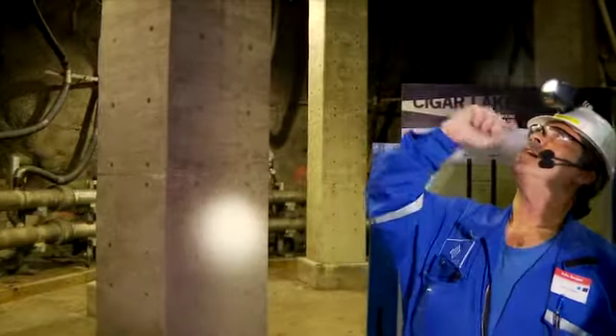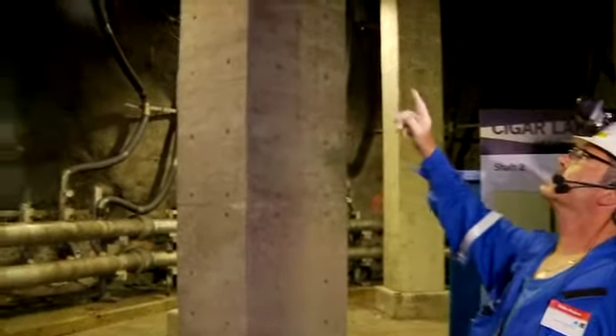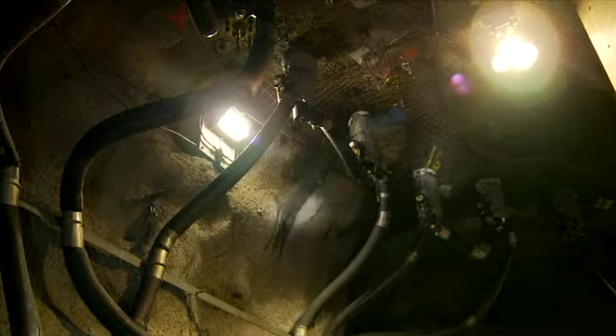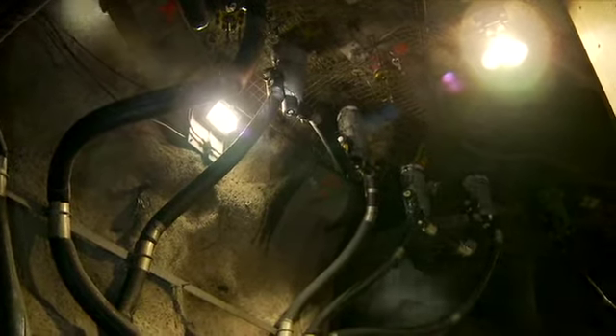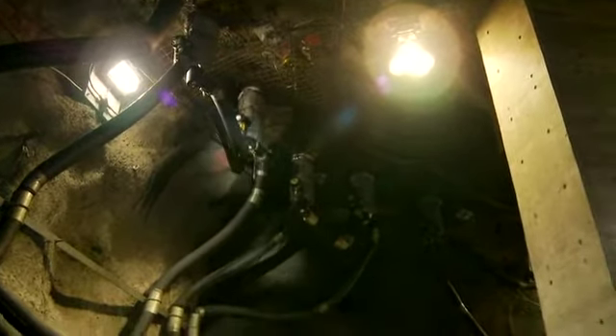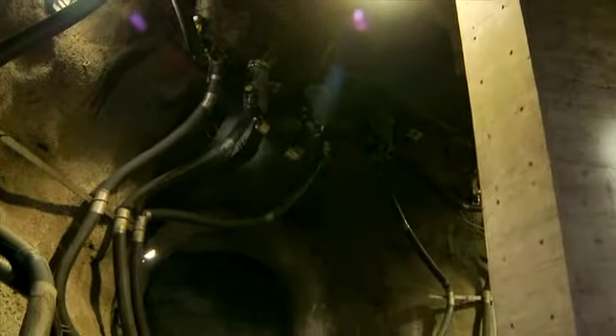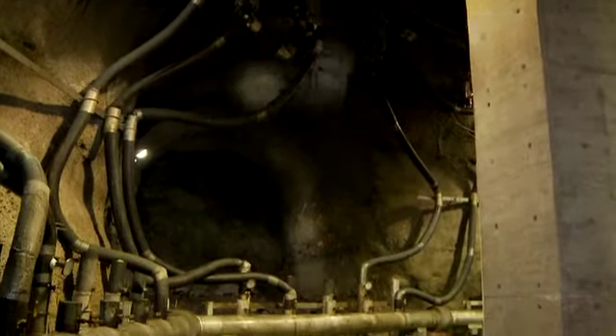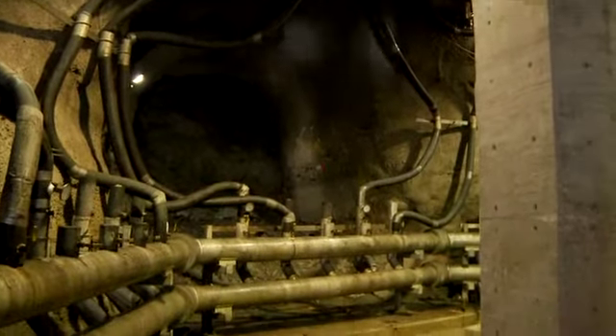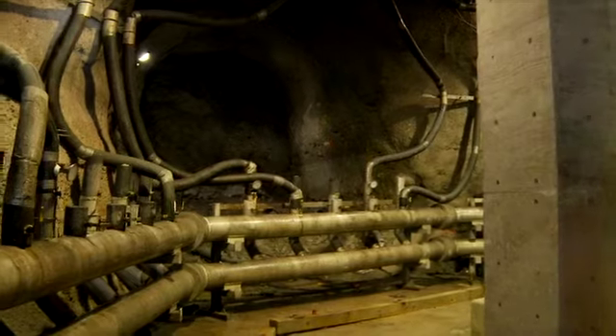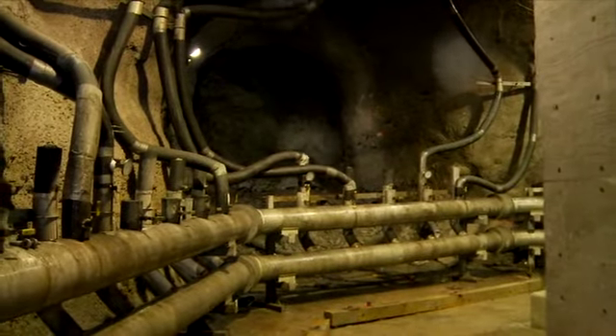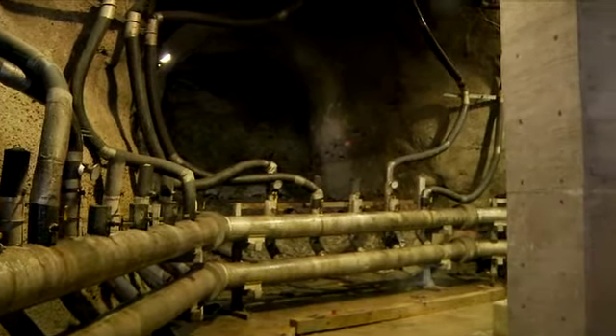Now you have along the back 23 holes, if you count them going around, and you see they're all like that there, and that freezes the perimeter around number 2 shaft all the way up to where we started sinking again at approximately 390 meters below surface. So you've got a line going in and a line going out. The line going out then goes to the next hole, so you always have 2 holes in series, and then goes back into the return line to go back to the heat exchanger.